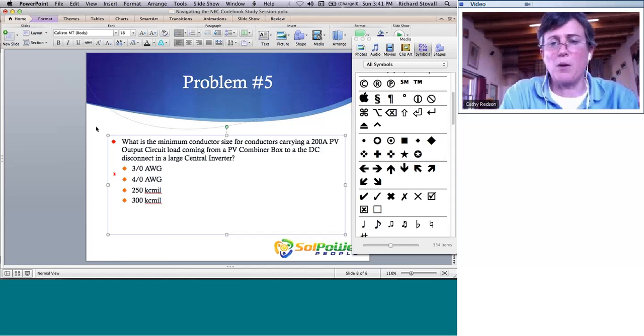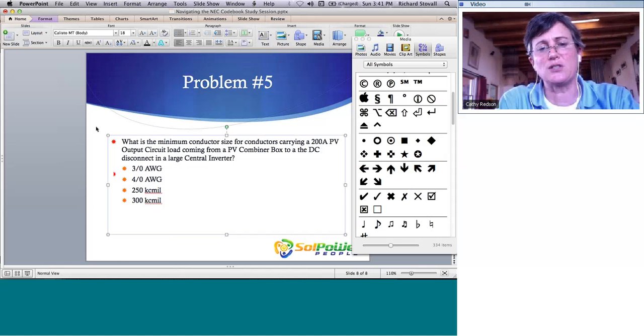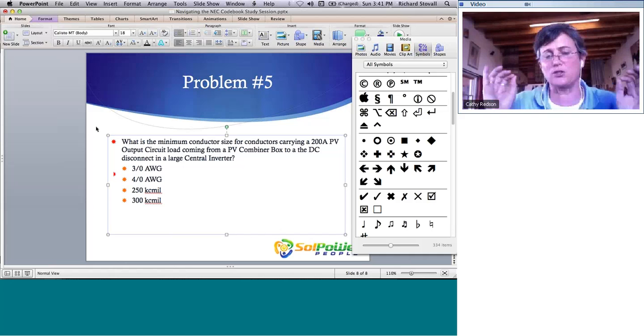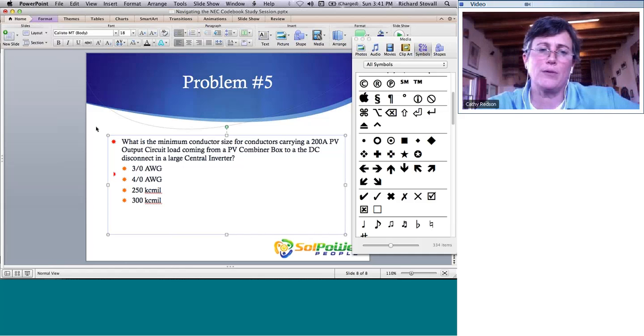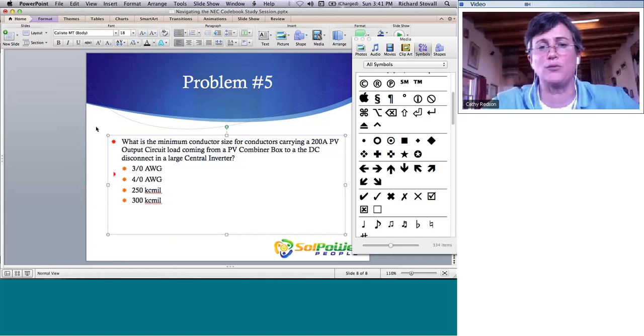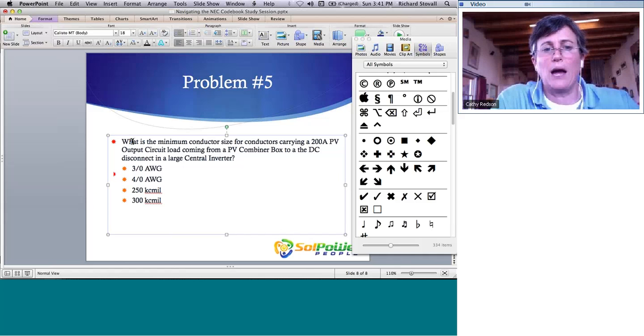First of all, coming from a PV output circuit, if you don't already know this definition, just about every conductor in any kind of PV installation is subject to this notion called continuous load. Electricians I've worked with call that the safety factor. What that means is that any time a conductor will be carrying current for a long period in excess of 3 hours, that's considered continuous duty or continuous load. So as a result, you need to always have a multiplier of at least 1.25 on what could be coming over that conductor.